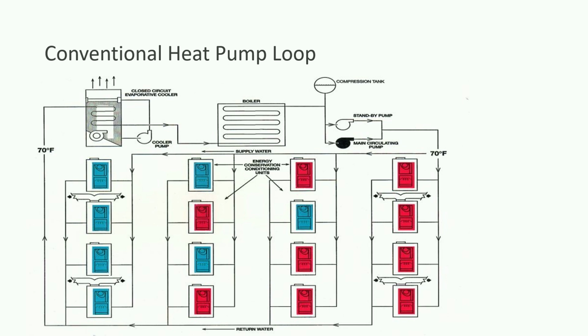The ones that are in heating are lowering the temperature of the water. The ones that are in cooling are raising the temperature of the water. So we're maintaining that 70 degrees. In cooling, you'll see entering water of 85, coming back at 100 degrees. The cooling tower rejects the heat. In heating mode, it's running out at 70, coming back at 55, 58 degrees. The boiler injects the heat.